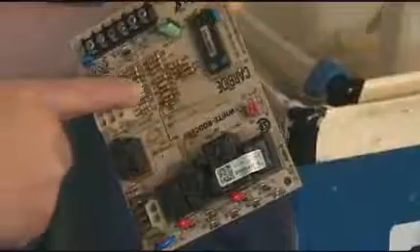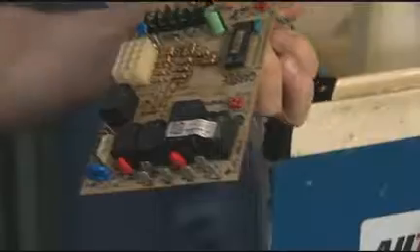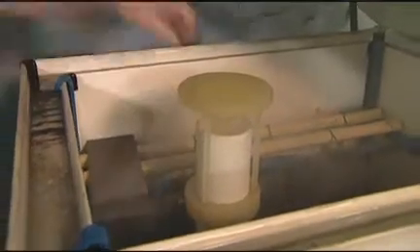And what you'll see here is it's starting to develop some corrosion. Right in here, you can see some on the back side as well. But in essence, what we're looking for is how good is the conformal coating on the board? How well are the components standing up? Are we getting ingress of the salt fog in under the relays, those types of things? And every day we'll take this component out, rinse it with deionized water, dry it, and put it back in a unit and make sure it's operating. That's the way we do the test with this.